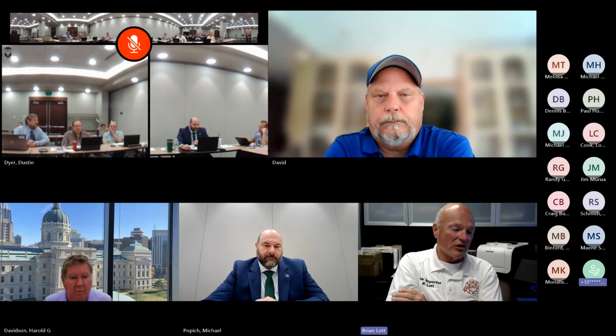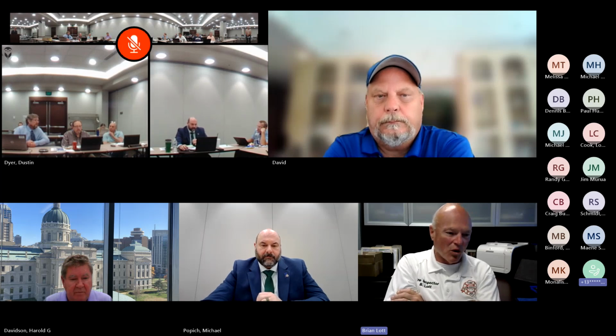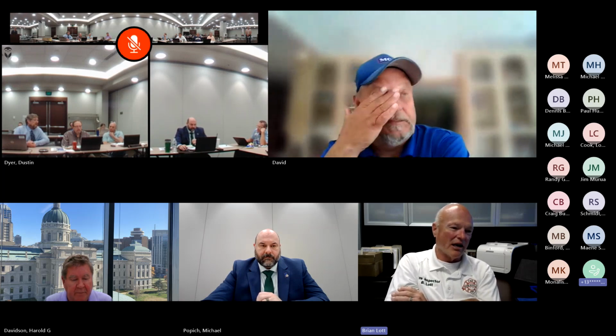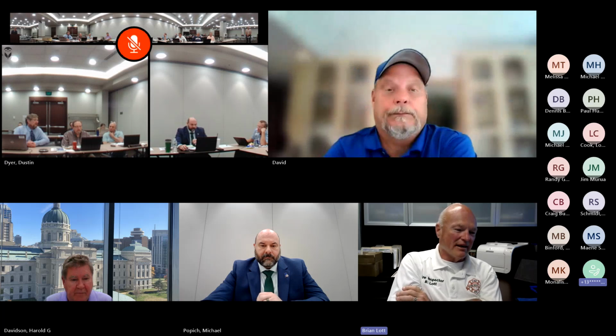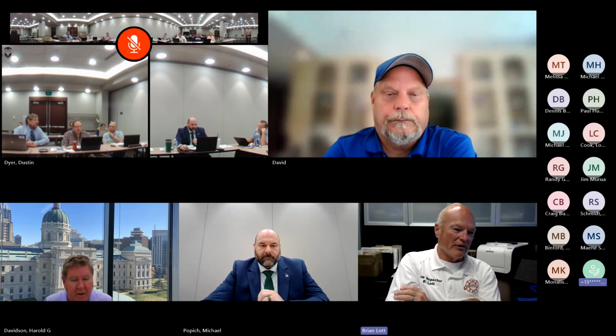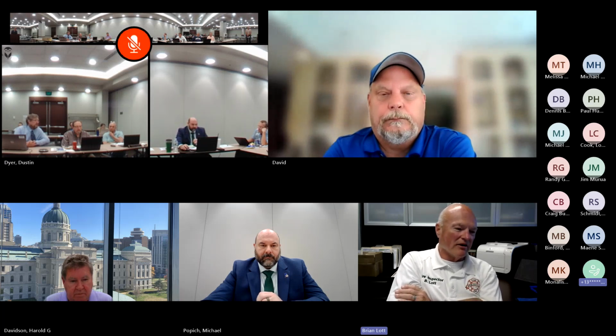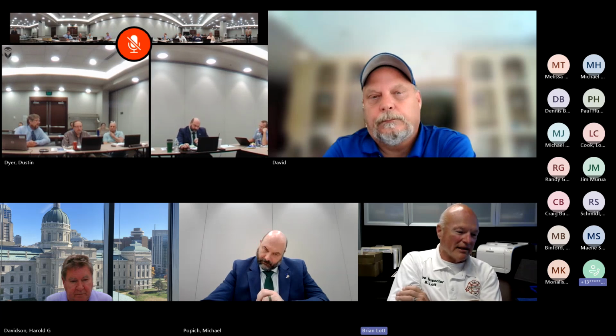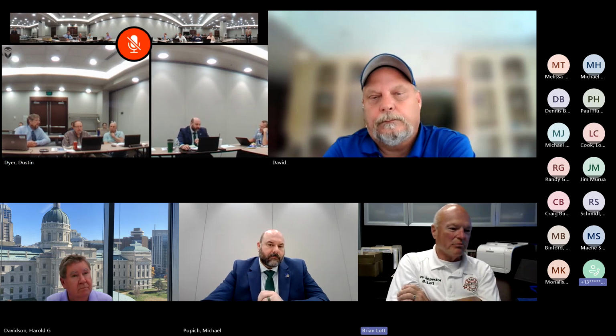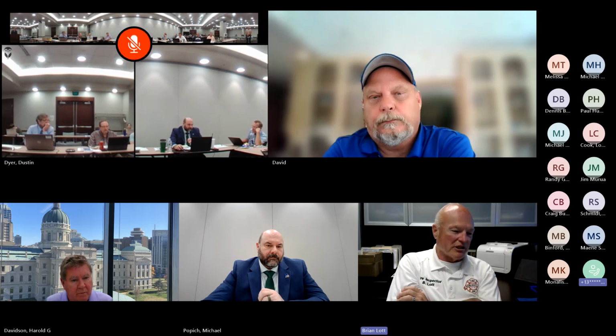So the good thing is they're all 155 heads. I did a surface temperature check, they're black exterior walls, so obviously it draws the heat. On a 92 degree day, we had 114 degrees on the surface right where the head was. So the 155 degree heads are probably not bad heads to have on there, but it's just going to be a longer response to pop the head versus the quick response heads, which is supposed to be installed.